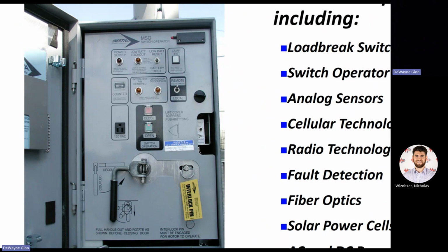The remote and local: when I put the switch in remote, that's for SCADA, and the control house has control of the switch. If I put it in local, when I'm standing in front of this, I can operate, open and close the switch right there. I put in a 120 volt plug, so I can plug test equipment into it as well. I put brush guards over the close and open buttons so I don't accidentally hit them.